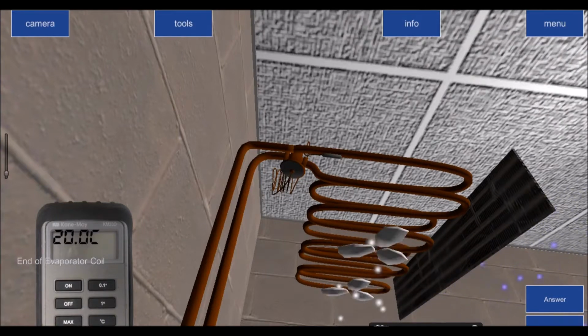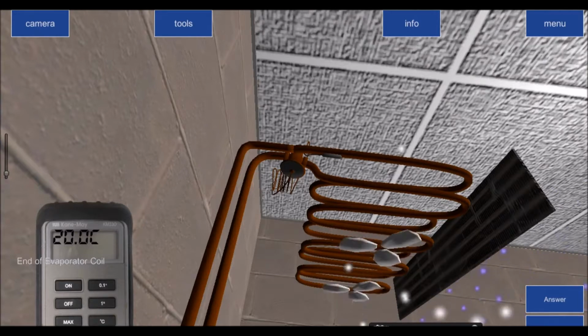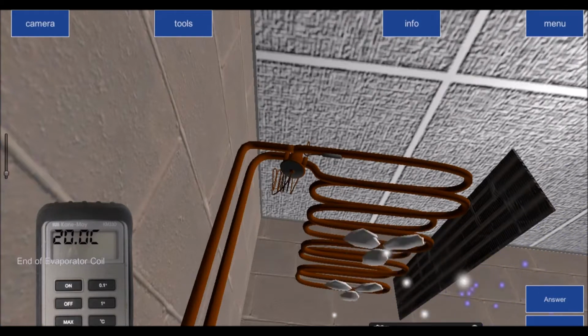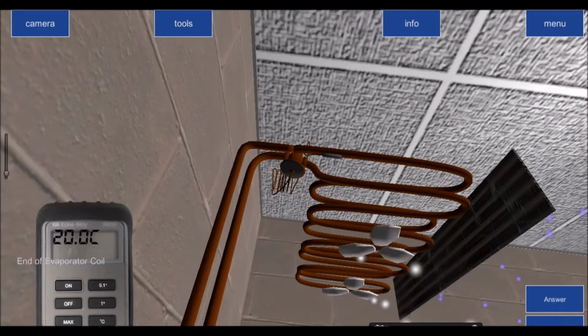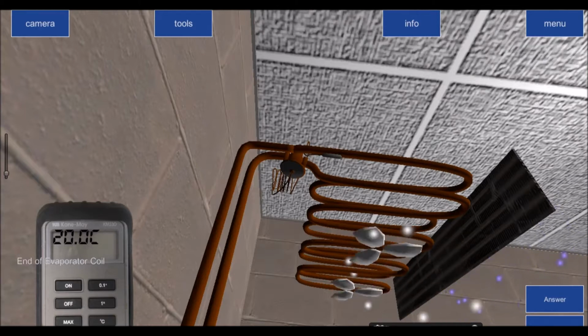on a comfort cooling split air conditioning system, we don't even worry about superheat, because the way they're designed, they have what's known as a suction accumulator, which will separate any potential liquid coming back from the vapor and only allow vapor to go back to the compressor. And often you might find, depending on how much work has to be done, how much heat needs to be removed, and what the temperature is, whether it's pull down temperature or holdover temperature, that on your return line coming from your indoor unit back to your outdoor unit, it will have a slight bit of liquid in it, or there will be a mixture of liquid.